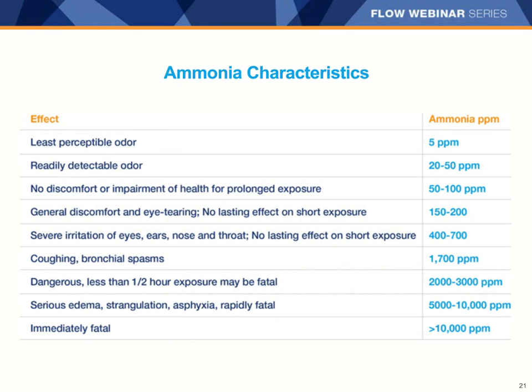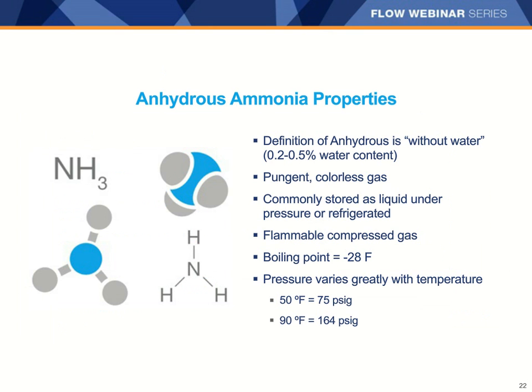Safety concerns are one of the primary drivers in SCR system design and selection. Ammonia characteristics shown above show why this is the case. At 150 to 200 ppm, we start with general discomfort, moving to 2000 ppm and up, which could be fatal. Let's start to look at different systems and reductants used. Anhydrous ammonia is one and is listed by OSHA as a hazardous substance. It requires a risk management plan and special permitting.